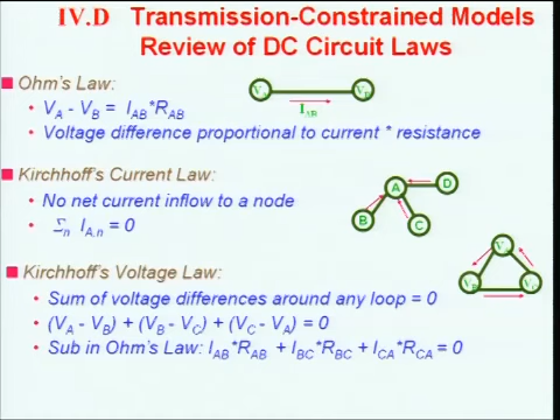Okay, there are some interesting implications of these laws for the physics and for the economics. You can use those simple equations to calculate stuff we're interested in, in particular to calculate load flow. If we know how much stuff is coming into the network from generators, and how much the consumers are taking out, we take those laws plus I squared R for resistance losses, put them together, and we can solve for the flow on each line plus the net injection at what I call the swing bus, because we don't know ahead of time how much losses we have. That's called the load flow problem, and we're going to hear a lot about that later this week from Daniel.